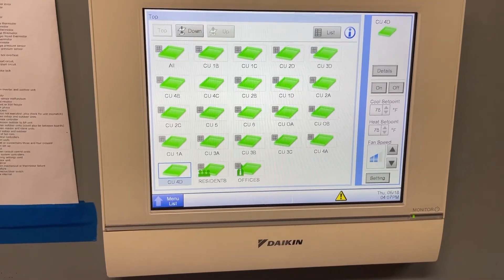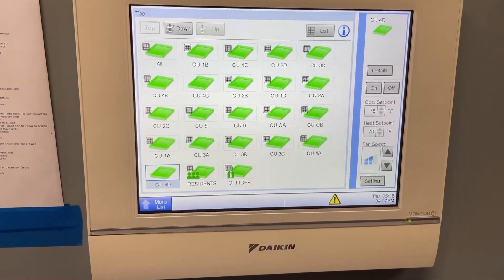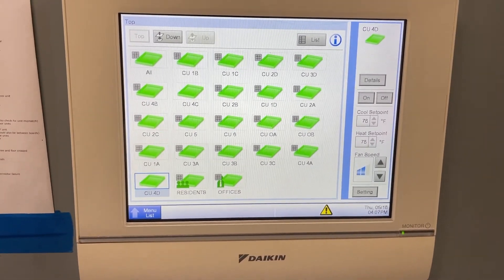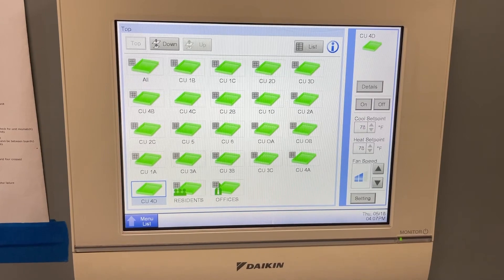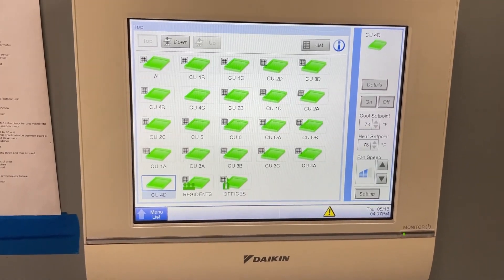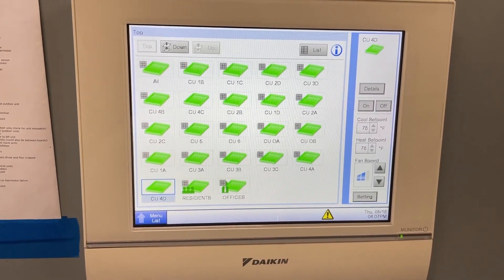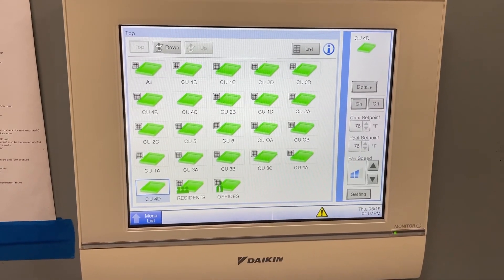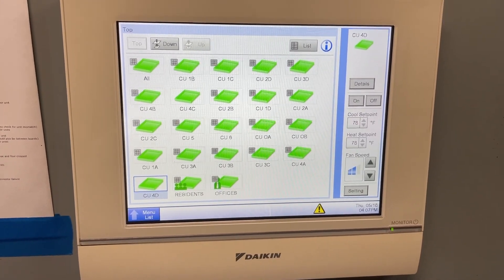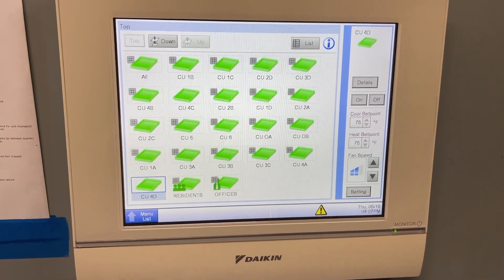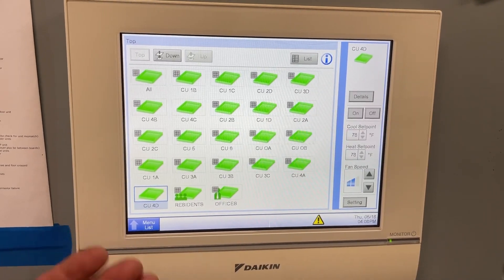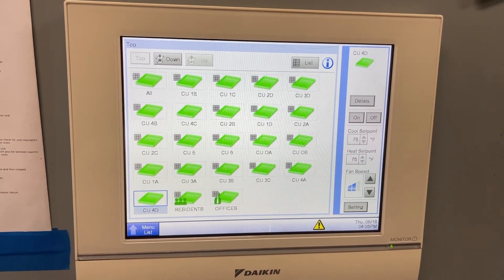The unit's out of alarm and it's going to run. I have to go run a service call — I've been on call this week and it's been one thing after another. I'll be back tomorrow to check the pump, check that flare nut for leaks, and do some follow-up to get everything right. But that's pretty much it for the diagnostic on the U9.